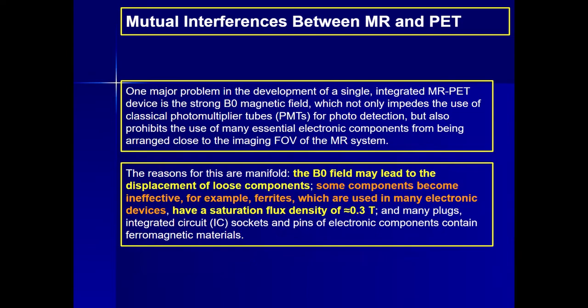One major problem in the development of a single integrated MR PET device is the strong B0 magnetic field, which not only impedes the use of classical photomultiplier tubes for photo detection but also prohibits the use of many essential electronic components from being arranged close to the imaging FOV of the MR system. The reasons for this are manifold. The B0 magnetic field may lead to displacement of loose components.